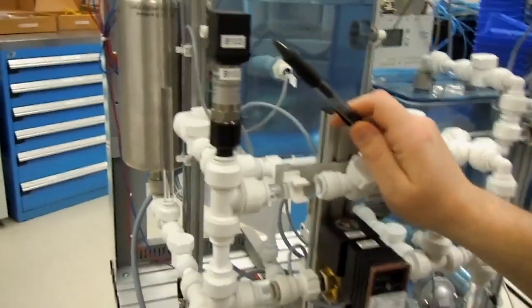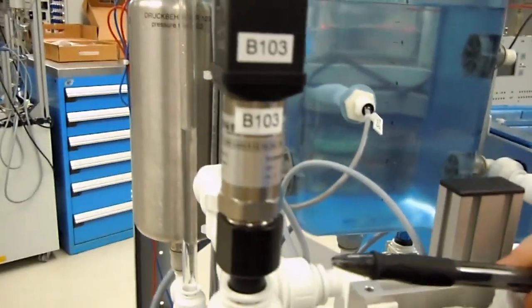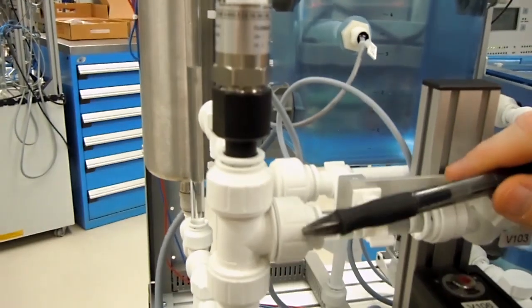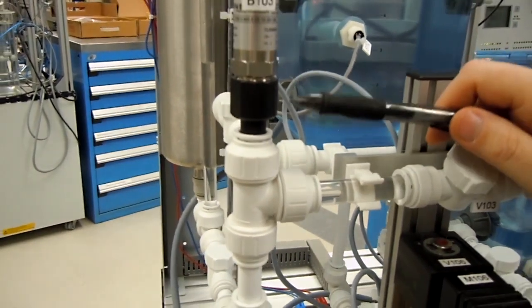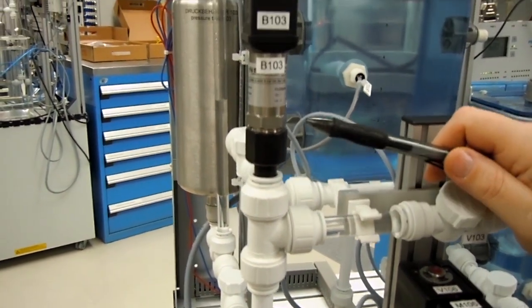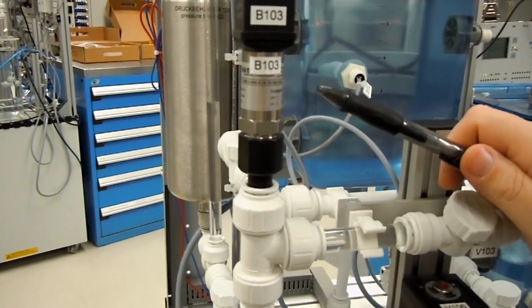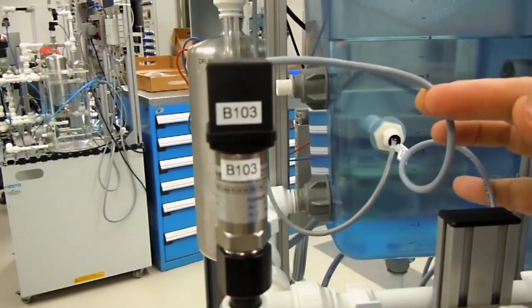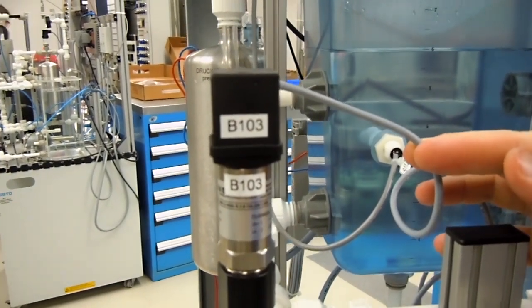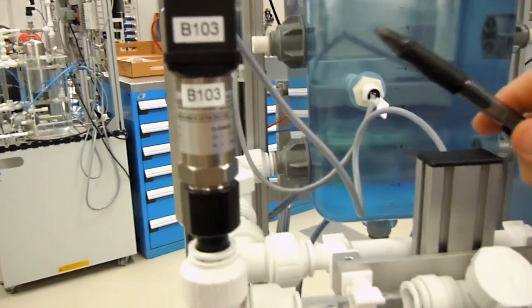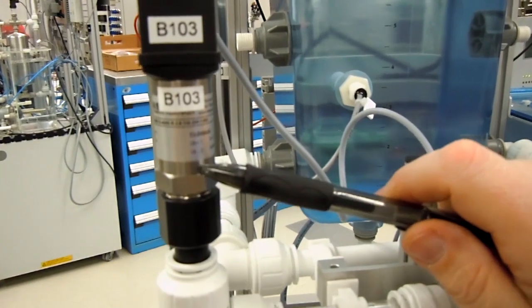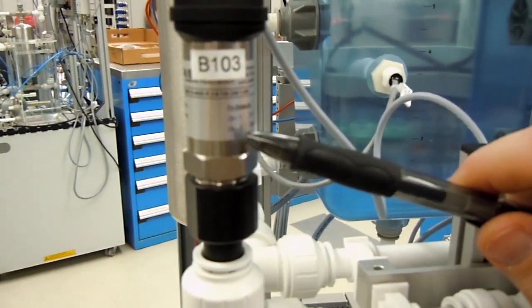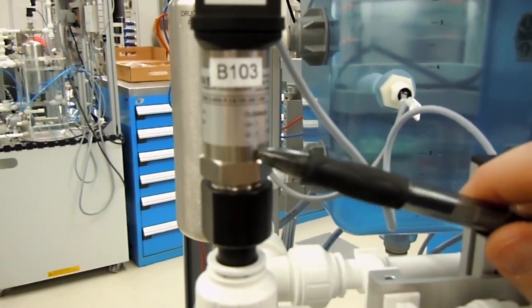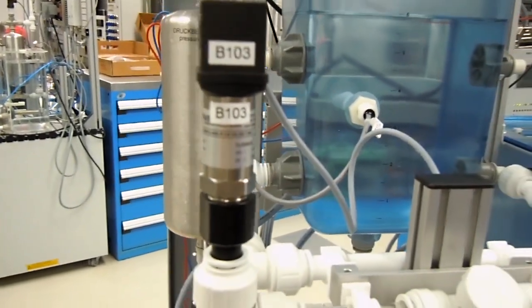Moving on to the pressure sensor up here, B103. This pressure sensor measures the pressure in this tubing, and its input is 0 to 400 millibar, and an output of 0 to 10 volts on this wire. So there's no converter required for this. This is about the most simple. And 0 to 400 millibar is about 0 to 5.8 psi. So that's the second analog sensor.